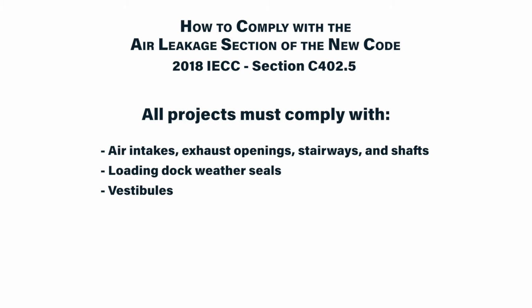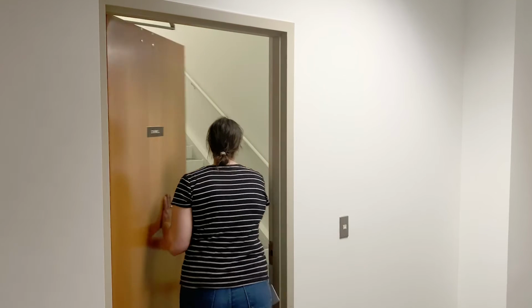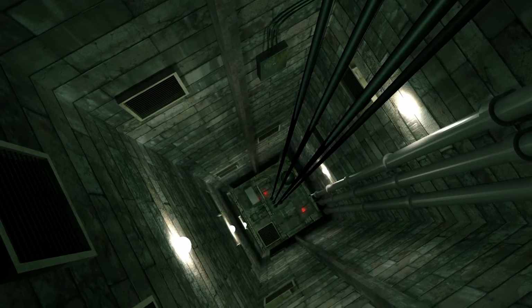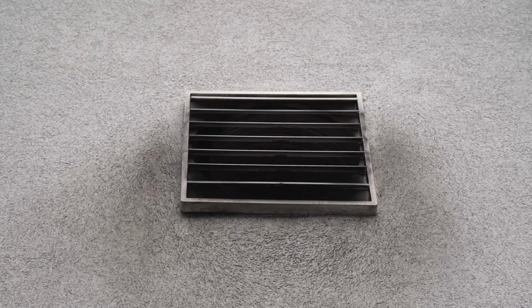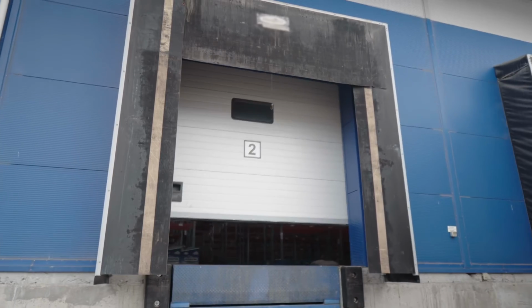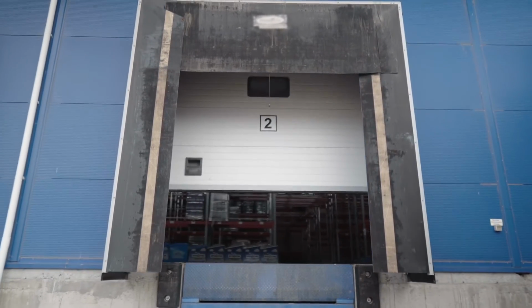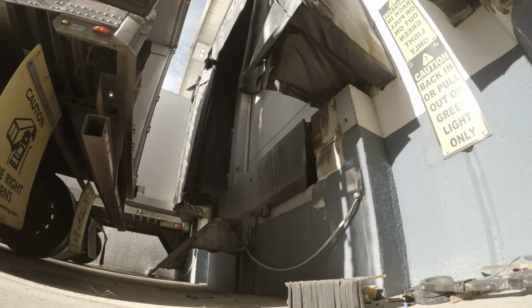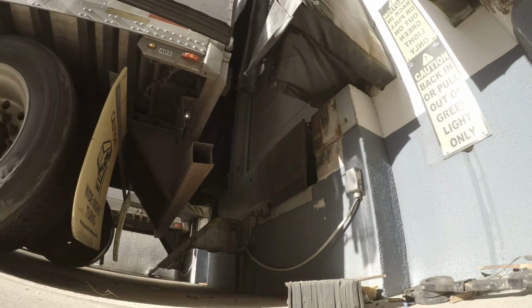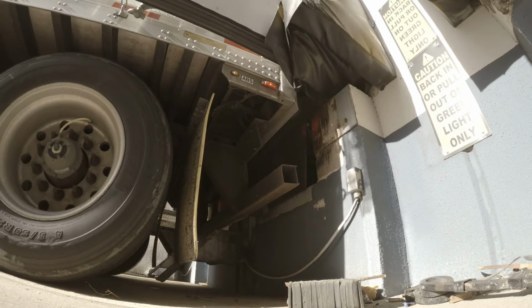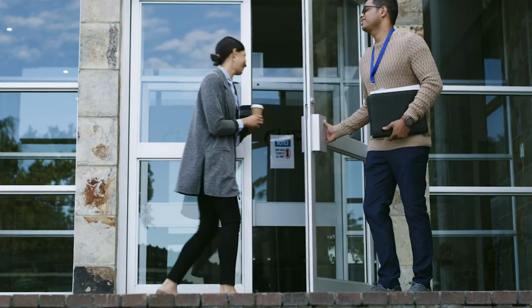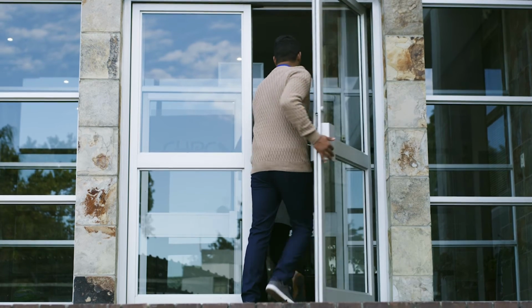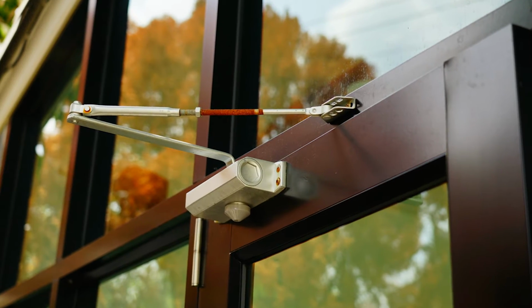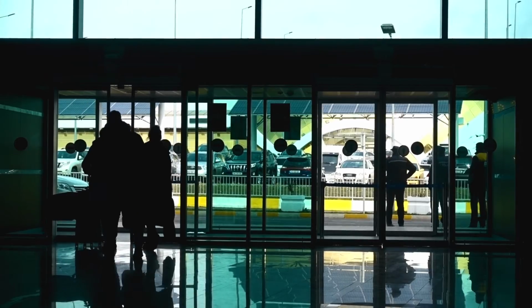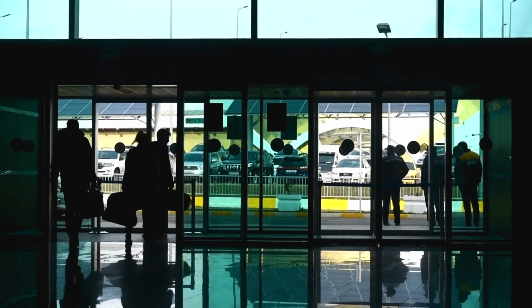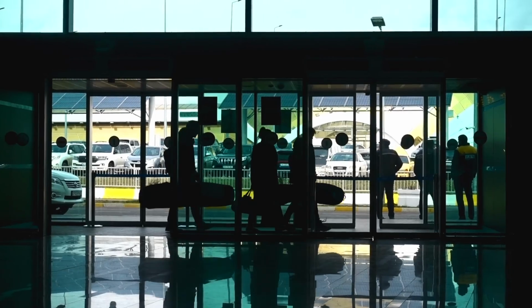First of all, dampers should be provided for stairway enclosures, elevator shaft vents, and other outdoor air intakes and exhaust openings integral to the building envelope. Second, cargo door and loading door openings should be equipped with weather seals that restrict infiltration and provide direct contact along the top and sides of vehicles that are parked in the doorway. Last but not least, building entrances should be protected with an enclosed vestibule, with all doors equipped with self-closing devices. One important thing to note here is that the interior and exterior doors should not need to open at the same time to allow for pass-through.